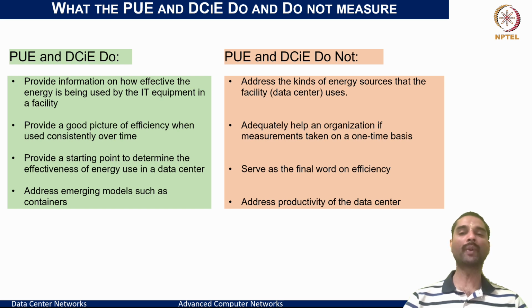We should also keep in mind that PUE and DCiE don't address the kinds of energy sources the facility uses. It's just the cumulative sum of energy used, regardless of the source driving it — some may come from internally produced power, some from the grid, and some from green energy. So the source of energy isn't accounted for in PUE and DCiE numbers.